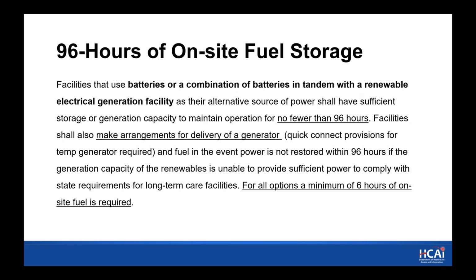And the facility shall also make arrangements for delivery of a generator. That would be provisions of a quick connect on the design on the site, and delivery of a temporary generator and fuel in the event power is not restored within 96 hours. Again, for all options, a minimum of 6 hours of on-site fuel storage is required.